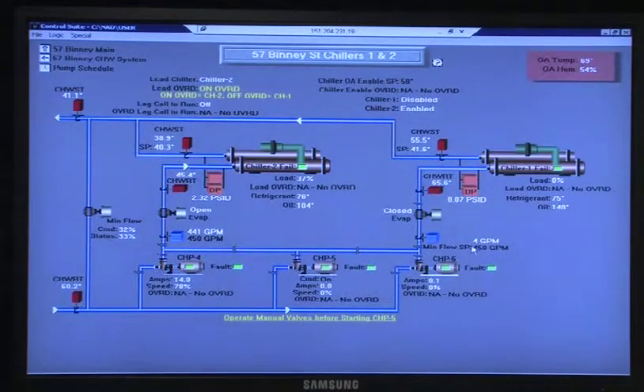The minimum flow set point here is 450 GPM. This says 4 GPM, just at the bottom of the scale. This valve's closed, but it should be looking at this one here, which is commanded open. So you have 450 here, and you have 450, that's good. So you've got 400-something flow to the chiller.